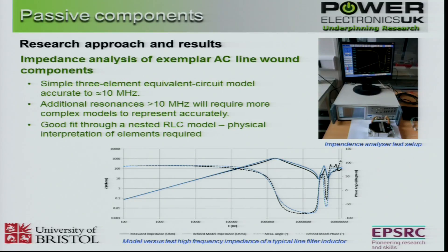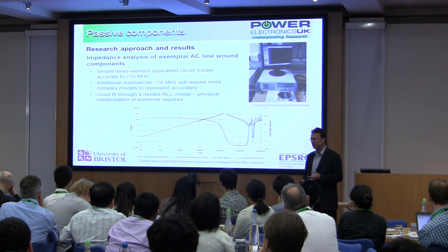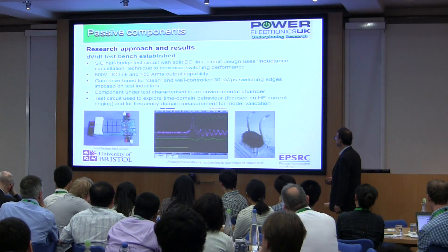The other area is looking at how high dV/dt affects the design synthesis of wound components. We need to understand the high frequency behaviour due to the higher spectrum the device is exposed to. So we've done some work on modelling state-of-the-art wound components, particularly at the higher frequency range above 10 megahertz - understanding parasitic capacitance, inter-turn parasitic capacitance, turns-to-case and earth parasitic capacitance - to develop a nested RLC model. The important thing moving forward is the physical interpretation of those elements: how do I get rid of a particular resonant effect, and how do I change the design to do that?